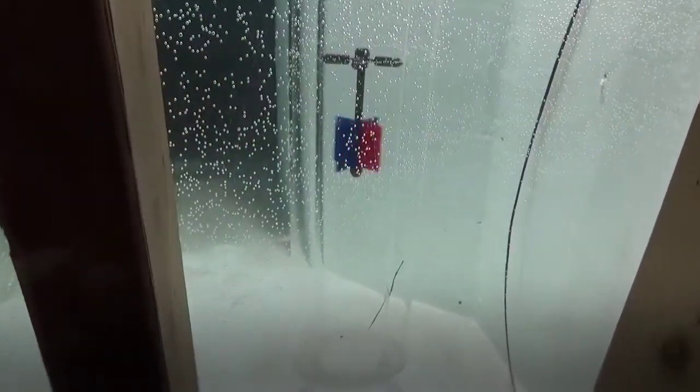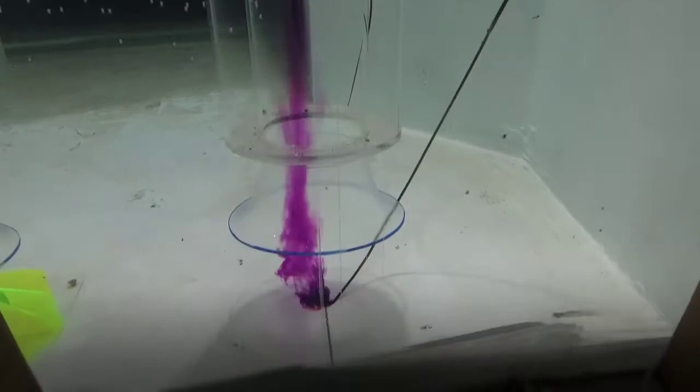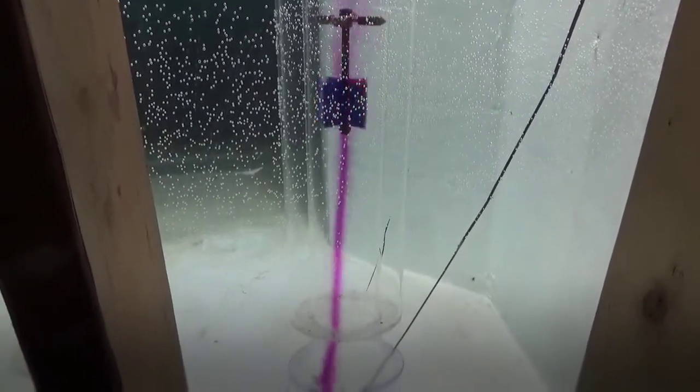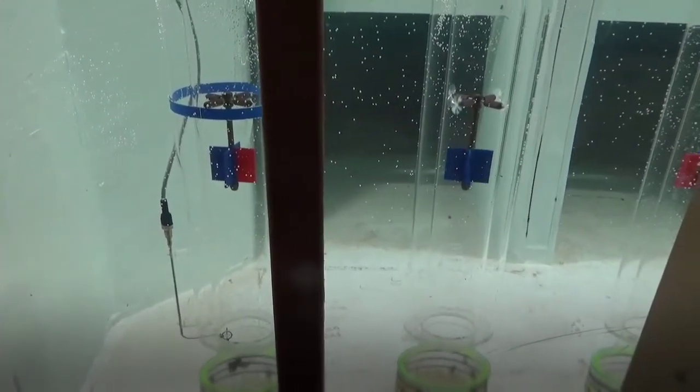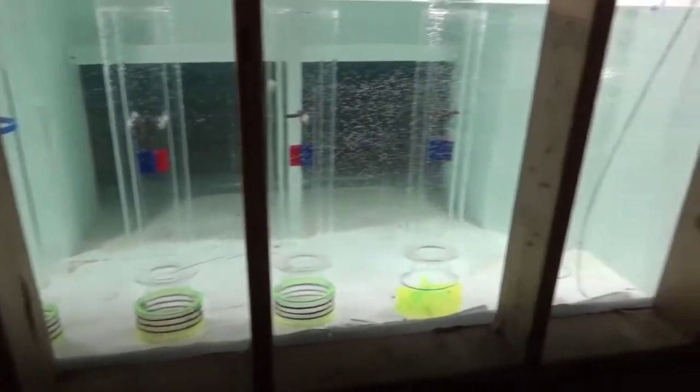But you can see pre-swirl remains very high. Same issue, we'll put the dye in, show you this still has strong floor vortex activity. So even whether you're running, you can see that. So it doesn't matter if it's backed up on the curve a little bit, it's still very, very adverse conditions on the pump. The pump itself will be a little more susceptible to this if it's back on the curve at 15,000 GPM or even 17,500. It's still going to like this vortex and pre-swirl even less than it does when it's at the rated flow at 20,000 GPM. But you can see the baskets still work extremely well on this end. So we'll be presenting all of this during a follow-up call with everybody attending that.